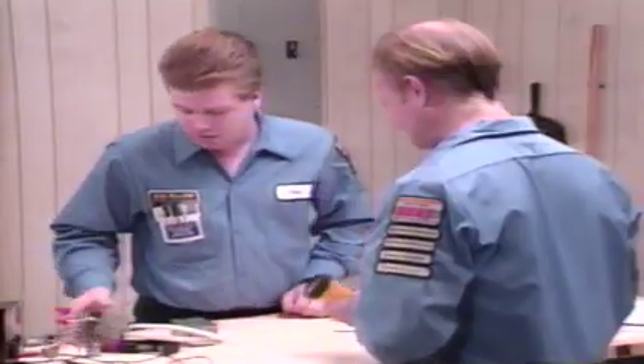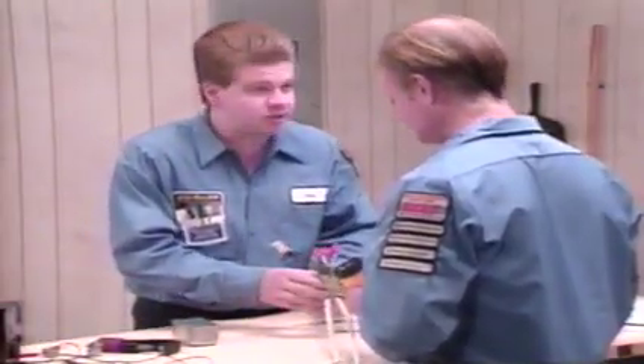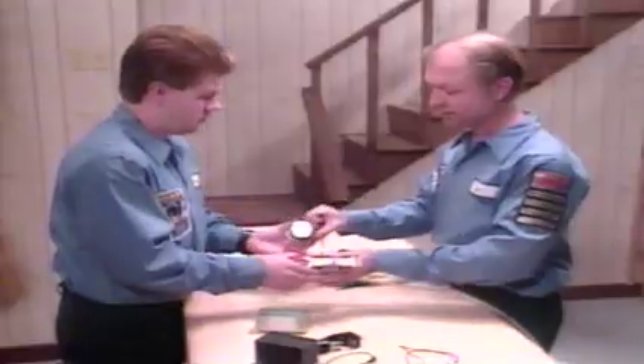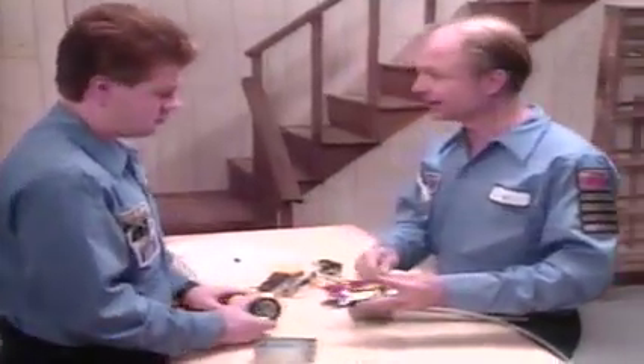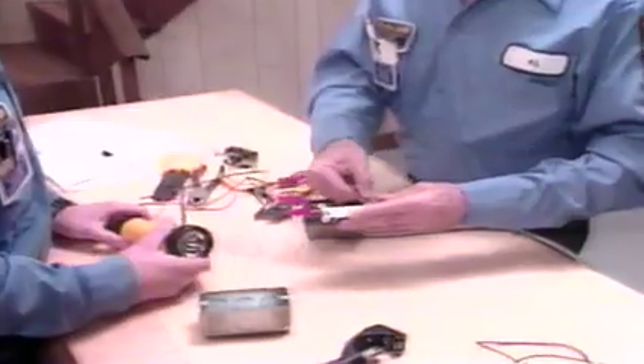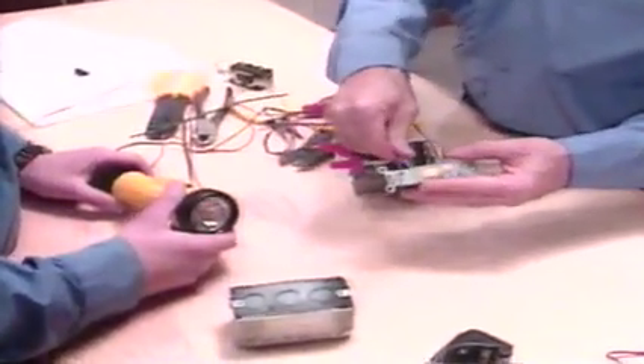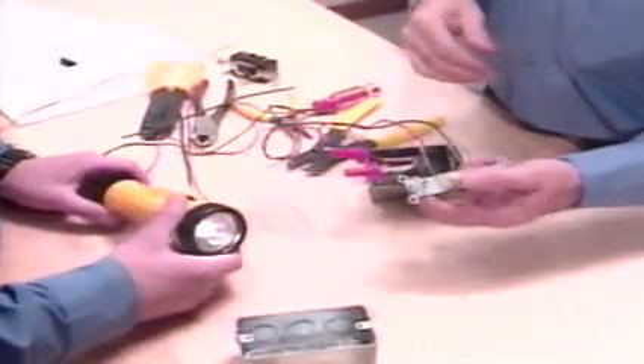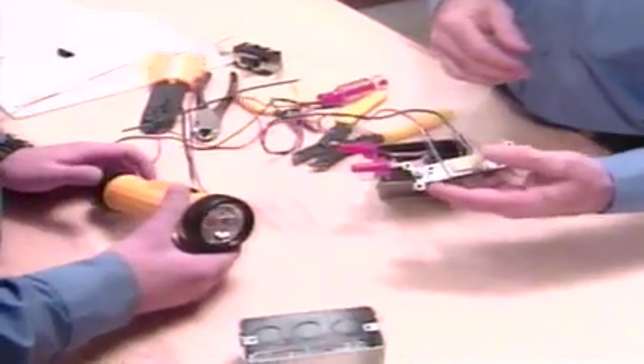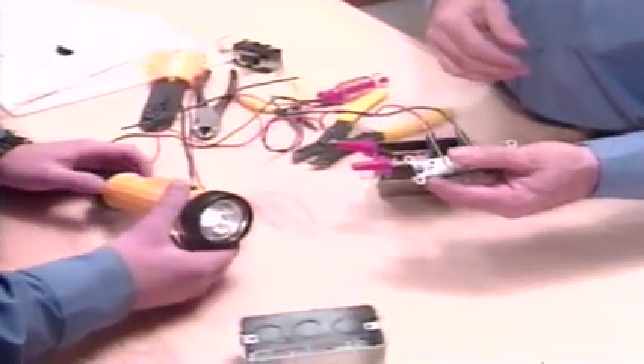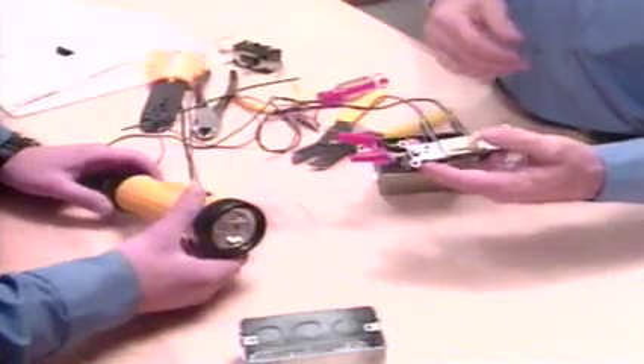So you don't use it with the power on? No, the continuity tester has its own source of power, so we always use it with the power disconnected. Can we use the continuity tester to check the switch we just wired? Yeah, sure we can. Here, you hold the tester. Since there's no power, we'll connect this clip, and flick the switch a couple times. When you turn the switch on, the light comes on. When you turn it off, it goes off. That's because the switch is good.